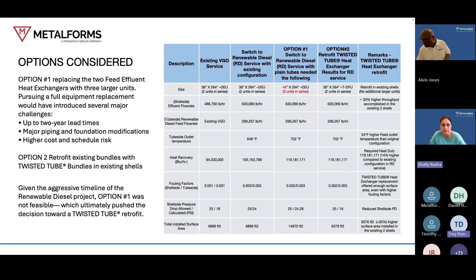When we came in, our solution was a bundle retrofit or revamp solution, putting twisted tube bundles inside the existing shells. There's a lot of information on this table, but essentially the duty requirement, or I would say the feed temperature requirement, was 702 degrees Fahrenheit, and the existing configuration would not have been able to meet that. We were able to meet that duty and keep within the same pressure drop by installing a larger surface area inside the existing shells.